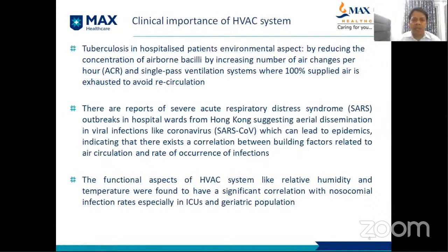For tuberculosis, once patients are admitted in the hospital setting, the environmental aspect is addressed by reducing the concentration of airborne bacilli, by increasing the number of air changes per hour, and by single-pass ventilation systems where 100% of supplied air is exhausted to avoid recirculation. There are reports of severe acute respiratory syndrome, SARS, outbreaks in hospital wards in Hong Kong. That leads to epidemics, indicating there is a correlation between building factors related to air circulation and the rate of occurrence of infections. The functional aspects of HVAC systems, like relative humidity and temperature, were found to have a significant correlation with nosocomial infection rates, especially in ICU and geriatric populations.